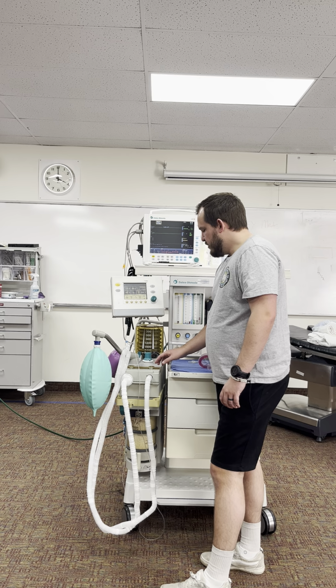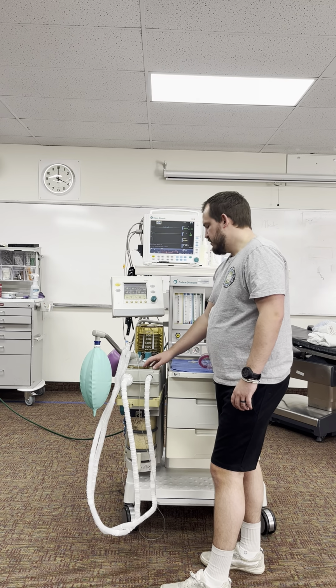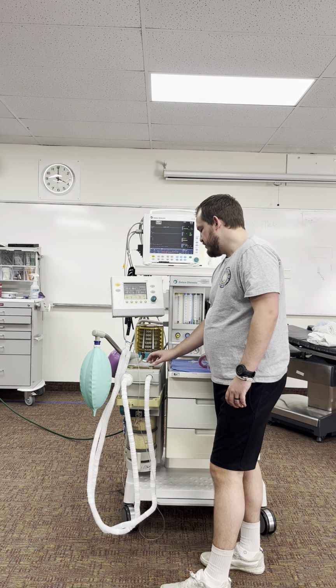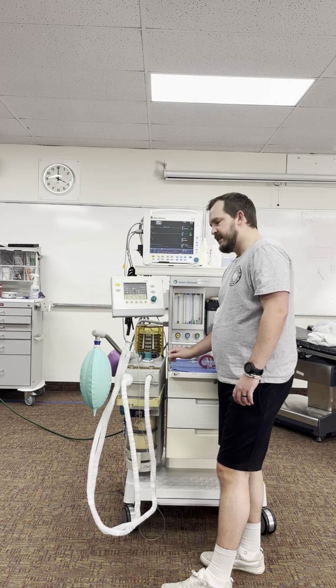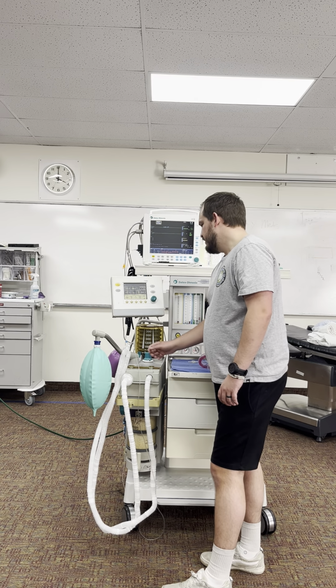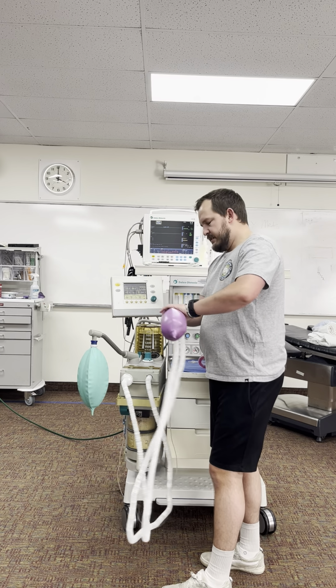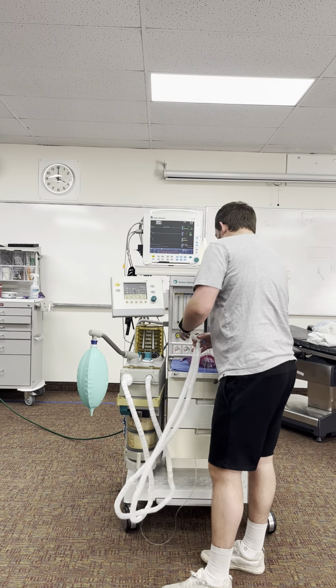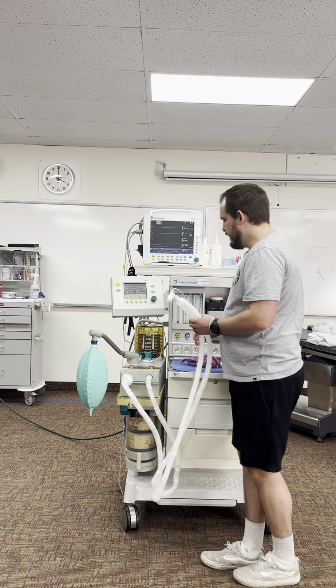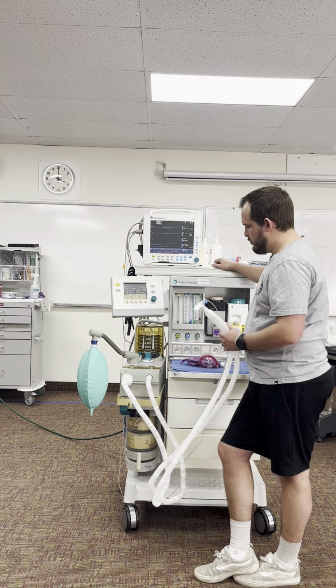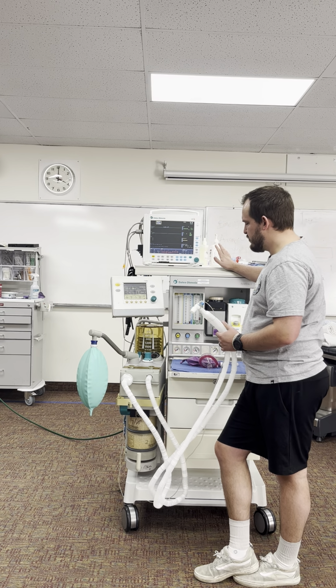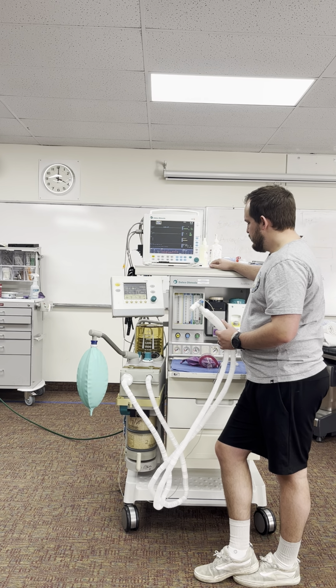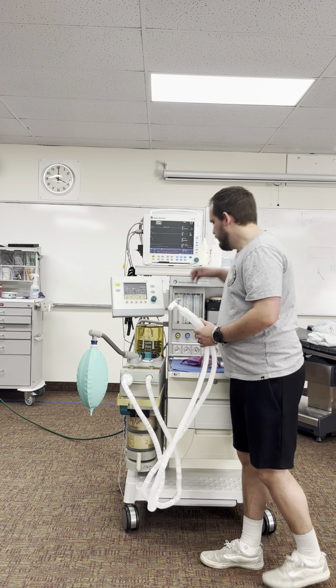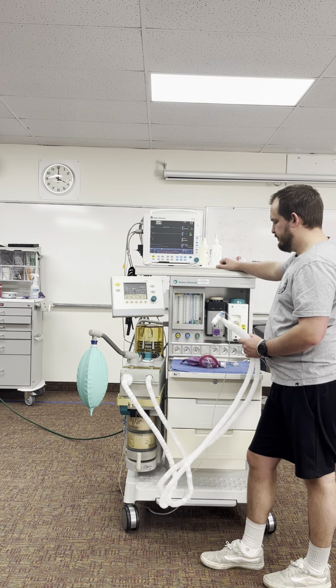And also like any cracks in any of the hardware. And then I'm gonna evaluate my one-way valves. So my inspiratory valve should only open on inspiration, and expiratory should only open on expiration, which is what they're doing. So that's good. And now I'm gonna disconnect, and this is to get me a disconnect alarm. And so now we just have to wait for the bellows to completely collapse, which take just a second longer.